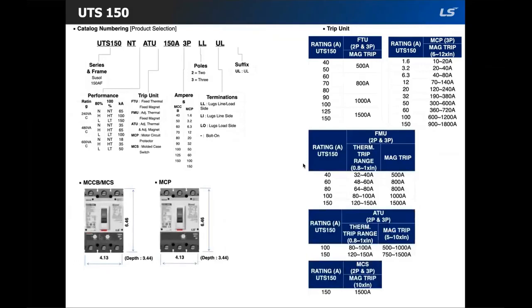So the second frame size would be UTS 150. For this one, there are 6 performance ratings: the 80% continuous current rated N, H and L types, and their 100% rated counterparts, the NT, HT, and LT. For this frame size, there are 5 types of trip units: the FTU, FMU, and then there is an ATU, which would be adjustable thermal and adjustable magnetic. And then you can also buy this in MCS and in MCP. For MCP, only 3-pole is available, not 2-pole. So that's one thing you've got to watch out for.